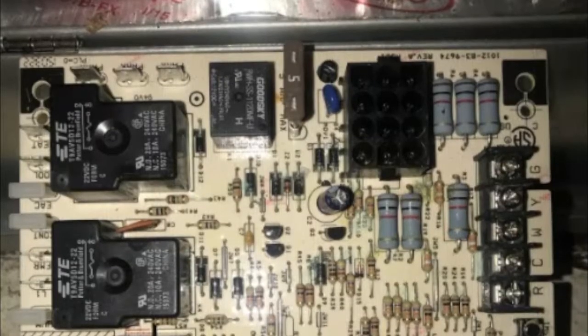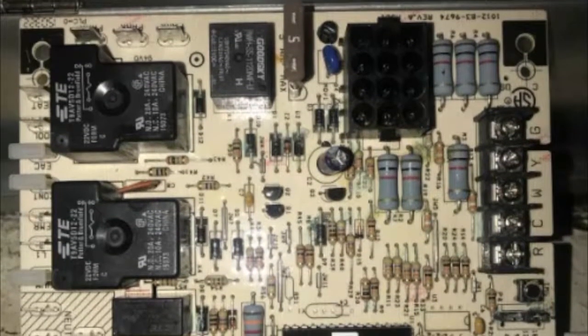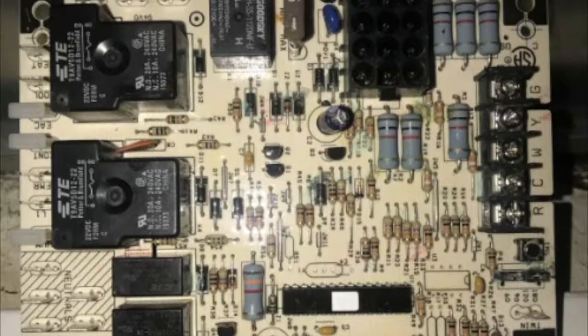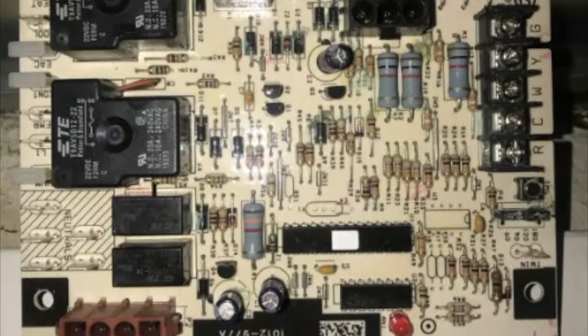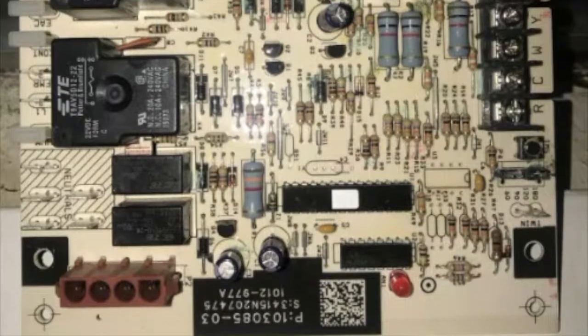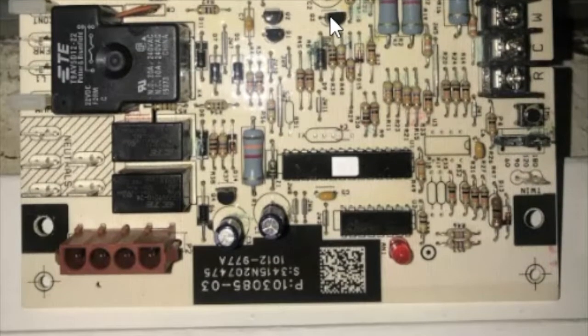After examining the air conditioner outside and finding that the unit had been installed for approximately 9 years, I entered the residence and found that the circuit board had been removed, the condensate drain line cut, and the system doors off. Upon examination, I determined that the circuit board had water damage in several areas.